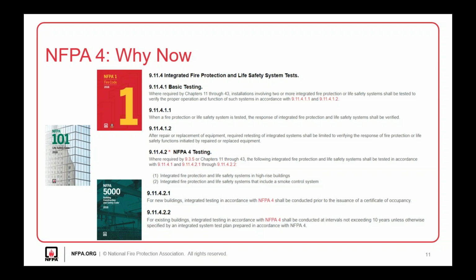But if you have a building that's a high-rise, or one of the integrated systems is a smoke control system, then the integrated testing must be completed in accordance with NFPA 4. And that integrated system testing must be completed before the issuance of the certificate of occupancy. It then goes on to note that if you have existing buildings, the integrated testing must be conducted at an interval not exceeding 10 years. It then allows you to specify a greater time if it's listed in your test plan and the AHJ also approves that. So as you can see, with the increase of smoke control systems and the construction of new high-rise buildings, you're going to start to see a lot more buildings that are going to require this integrated testing per NFPA 4.